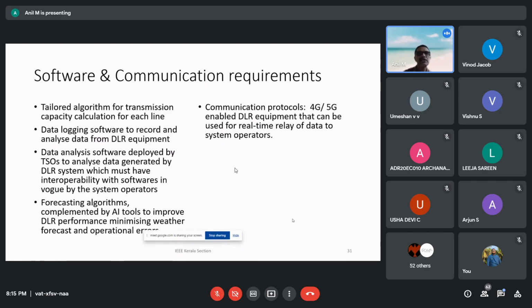Software and communication requirements: a tailored algorithm for transmission capacity calculation for each line, data logging software to record and analyze data from DLR equipment, and data analysis software deployed by TSOs to analyze data generated by the DLR system, which must have interoperability with software used by system operators. Forecasting algorithms complemented by AI tools improve DLR performance, minimizing weather forecast and operational errors. Communication protocols: 4G or 5G enabled DLR equipment can be used for real-time relay of data to system operators.